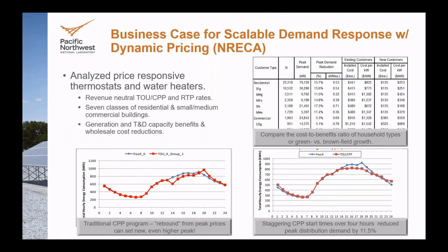If you weren't using something that captured the individual end-use behavior or the time series simulation capabilities, you would miss this, and you might deploy a demand response based off of this red dot here and say everything will be great. And then once you get it deployed, you find out your system actually gets significantly more overloaded than it was, and now you have to deal with that problem. So this is a very good highlight of where the capabilities of GridLAB-D are very useful for evaluating some of your smart grid technologies that may not lend themselves to traditional analysis.